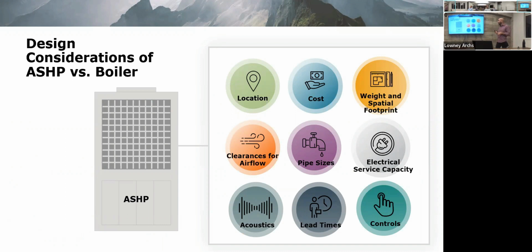They're heavier and larger than gas boilers. You need clearances around this equipment for outdoor airflow. Pipe sizes: you will need slightly larger pipes for these systems because the temperature difference they can provide is lower than gas systems. You will need larger electrical service capacity in your building because you're adding additional electrical equipment, which is not small. It's replacing the gas.